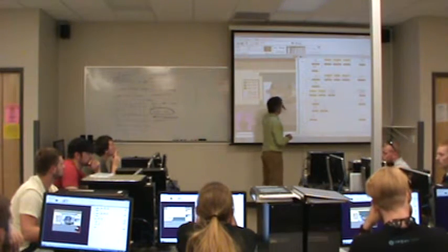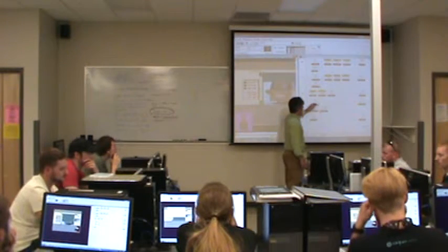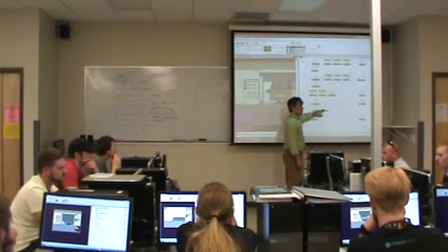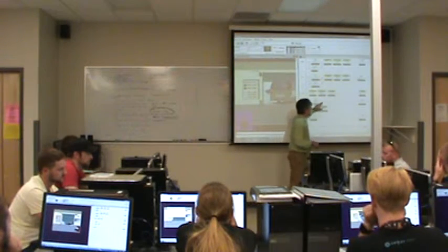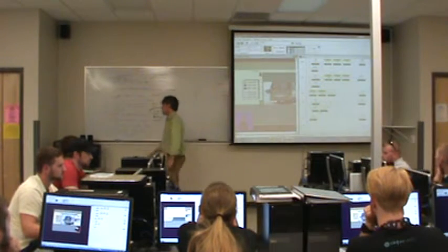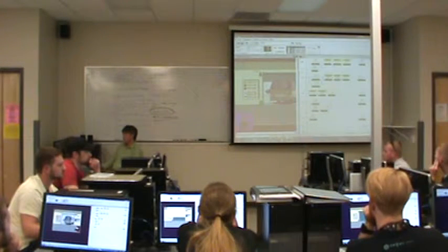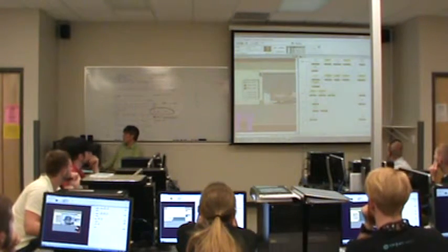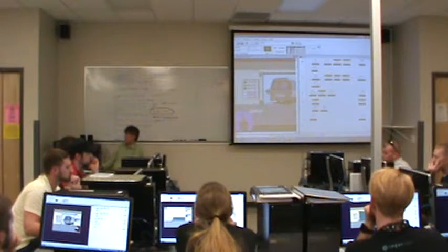On the other hand, if the door goes all the way up, then the upper limit switch will be made solid, and it won't matter whether this is flashing or not, because once again, the motor up will shut off, but this will keep the open lamp on consistently, constantly. Let's try it and see. If we hit open and let it go all the way to the top, the open lamp should flash. Once the door reaches the top, the open lamp should stay on solid. So let's watch. It flashes, and it's on solid. So that works the way I want it to.